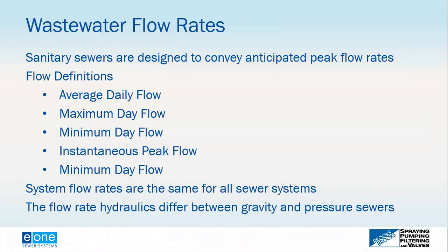Sanitary sewers are designed to convey wastewater, and you want to design a system to convey the anticipated peak flow rates, ensuring pipelines, lift stations, and treatment plants are sized for the most wastewater produced instantaneously. Key flow definitions include average daily flow — the average flow within the service area, generally presented as a per-resident breakdown. More critical are the maximum day flow, minimum day flow, and instantaneous peak flow, also called peak hydraulic flow or peak hourly flow. Pipe sizing must ensure all flow can be conveyed regardless of whether it is a gravity or pressure sewer system.